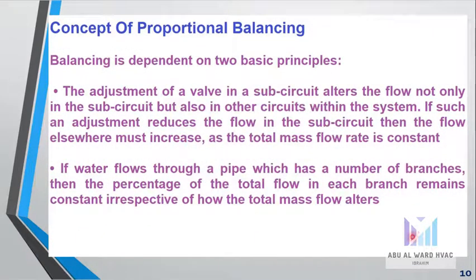Concept of proportional balancing: balancing is dependent on two basic principles. First, the adjustment of a valve in a sub-circuit alters the flow not only in that sub-circuit but also in other circuits within the system. If such adjustment reduces the flow in the sub-circuit, then the flow elsewhere must increase as the total mass flow rate is constant. Second, if water flows through a pipe which has a number of branches, then the percentage of the total flow in each branch remains constant irrespective of how the total flow alters.